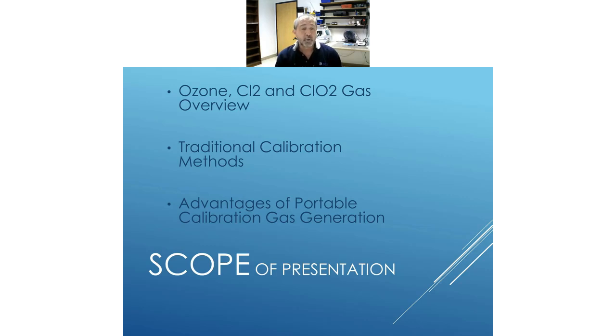So first we're going to tell you what we've got. The scope of the presentation is we're going to go over what ozone, chlorine, and ClO2 are, traditional calibration methods, and then the advantages of being able to generate these calibration gas levels on demand in portable gas generators.